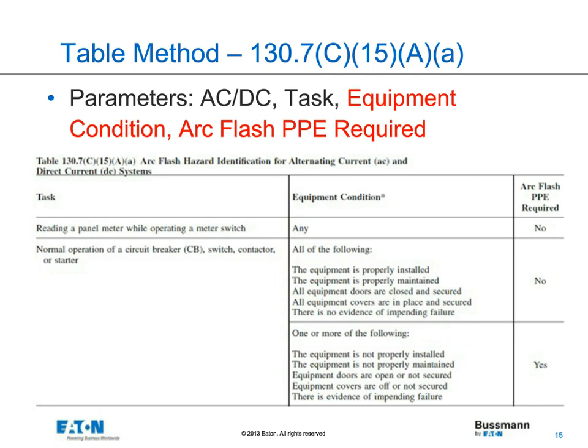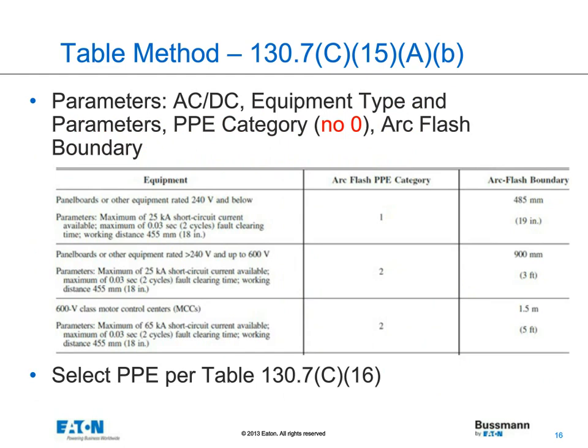So the first step using the table method is to refer to this table. It's a task table, but it tells you whether or not you need PPE, and we factor in the equipment condition in that analysis. Once we have gone to that first table, looked at our task, and found out that yes, PPE is required, we would go to the second table and look at our specific tasks. This is where we have not only specific tasks and equipment, but also parameters.